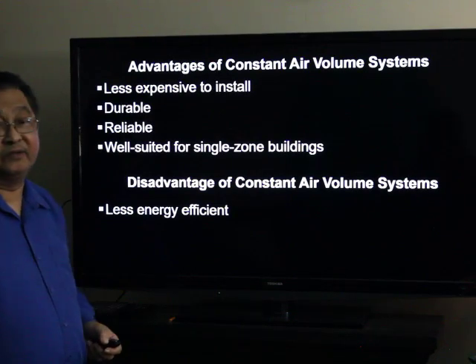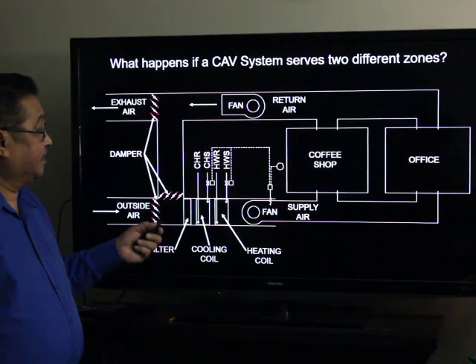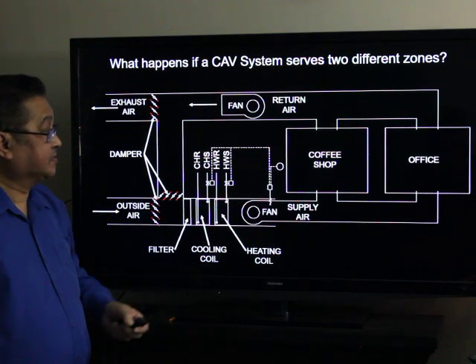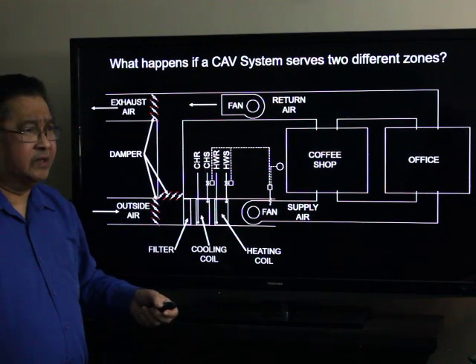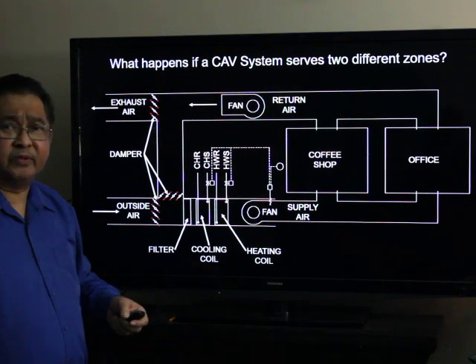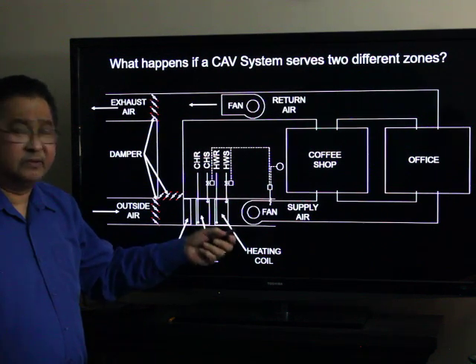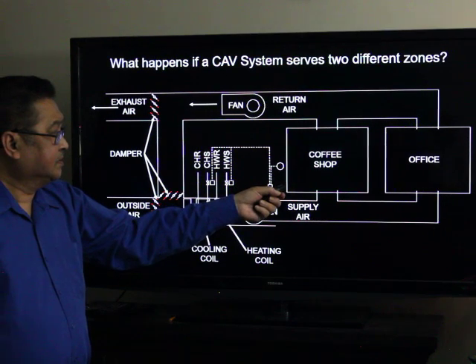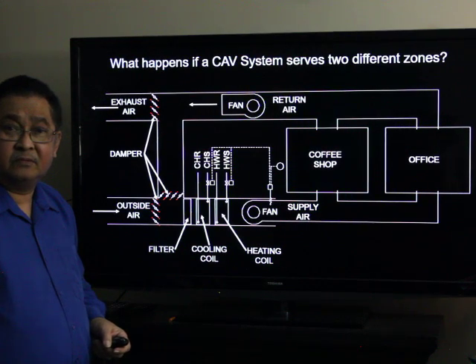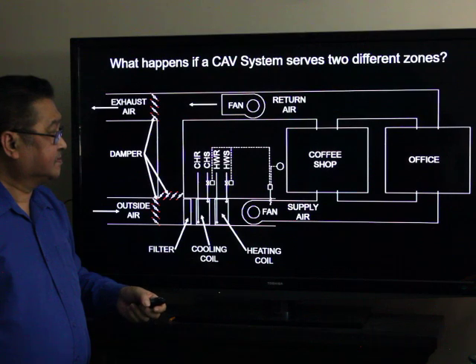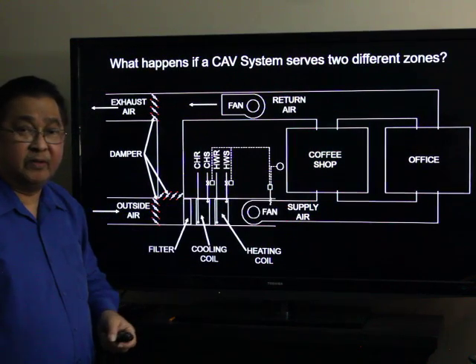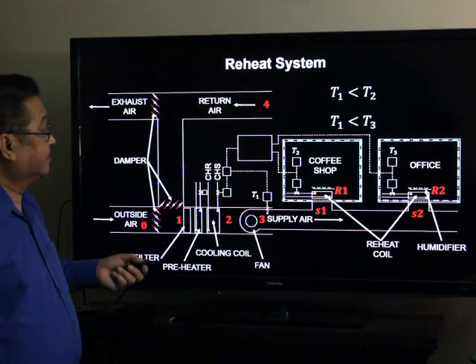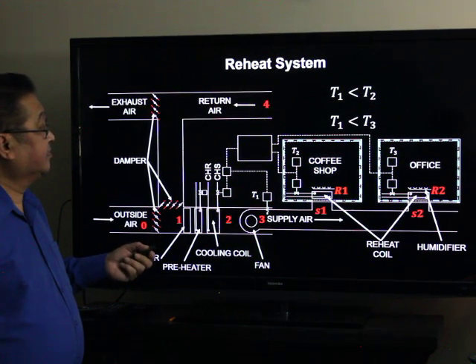Disadvantages: it is less energy efficient. What happens if it serves two different zones? You have the supply air serving two different zones — a coffee shop and an office. For example, at 6:30 in the evening, the office is already closed but there are two employees working overtime. The coffee shop is at peak hours with lots of people, so we need more cooling in the coffee shop and less cooling in the office. You will experience discomfort in the coffee shop because it's too hot. You cannot just adjust the temperature setting because decreasing it will make the office too cold. That's why there is a modification of the constant air volume system, which is a reheat system.